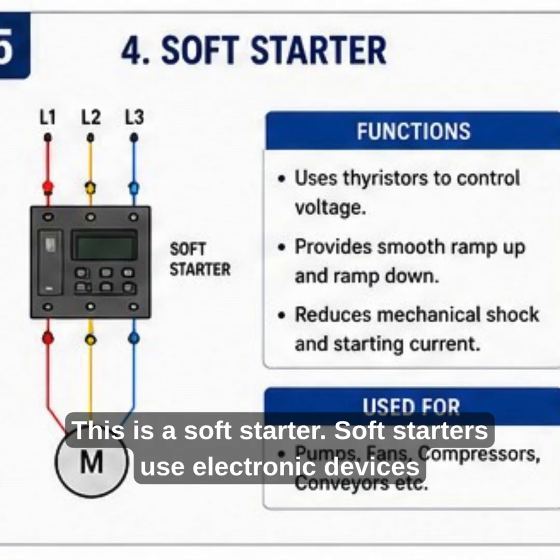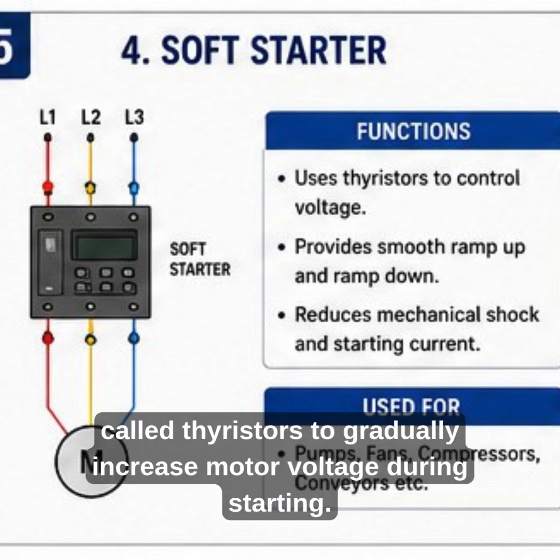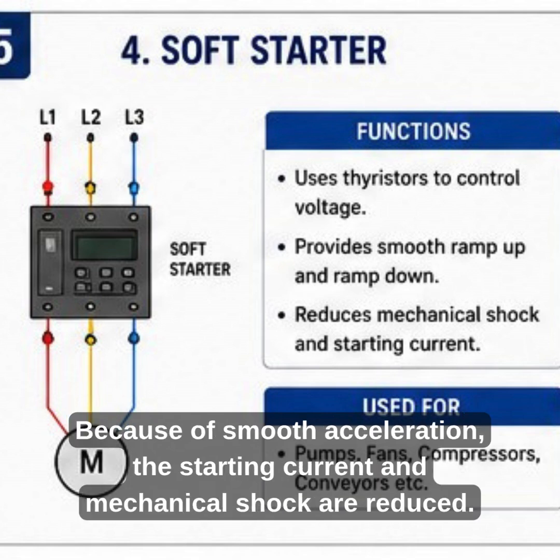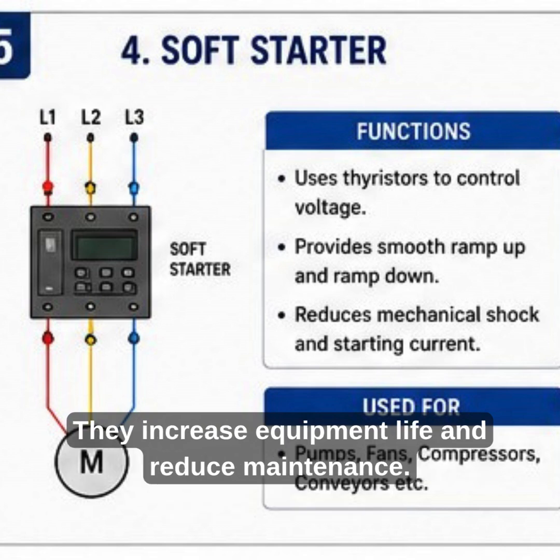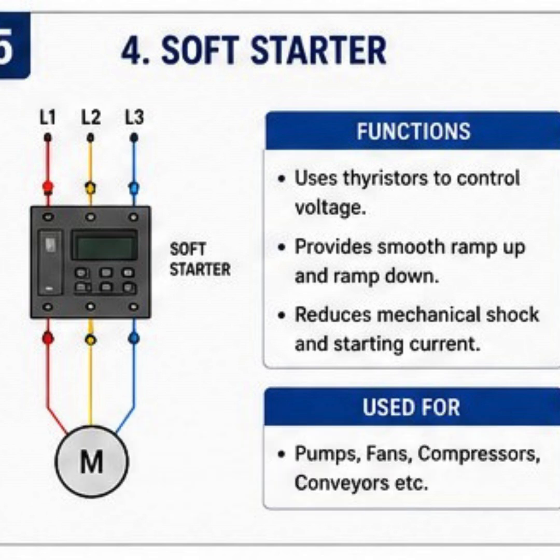This is a soft starter. Soft starters use electronic devices called thyristors to gradually increase motor voltage during starting. Because of smooth acceleration, the starting current and mechanical shock are reduced. Soft starters are commonly used in pumps, fans, compressors and conveyor systems. They increase equipment life and reduce maintenance.